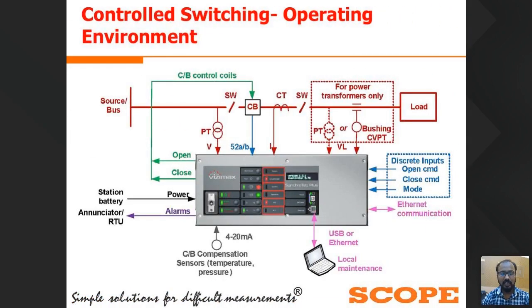Now we will see what inputs are required for the control switching device to do the control switching of any equipment. In the image you can see a control switching device, and now we will see the inputs required for the control switching. First of all, we are taking the close and open command inputs from the TNC switches and the Bay Control Unit, that is, from the SCADA system. First of all, we have to keep in mind that the control switching device is used only for the manual operation of the equipment.